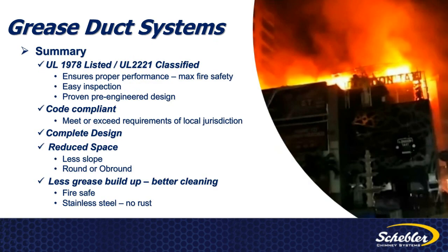So, to give you a whole summary here: UL 1978 listed and classified products really ensure proper performance and maximum fire safety that you may not be sure you're going to get with a field fabricated product. Easy to inspect. There are simple installation instructions and drawings for the code official to evaluate and approve. It's code compliant.